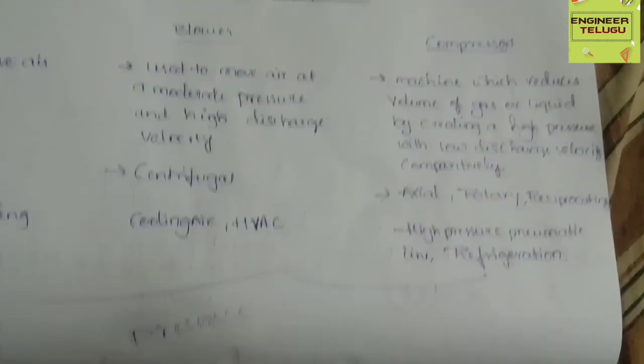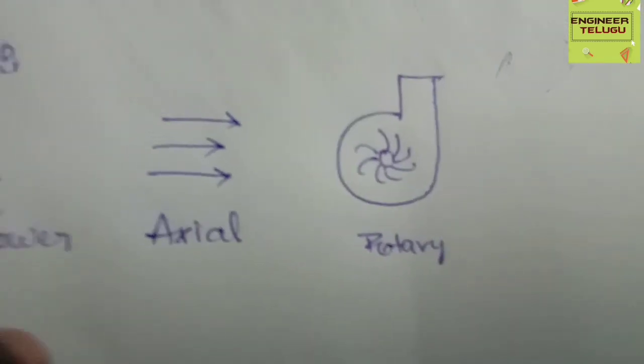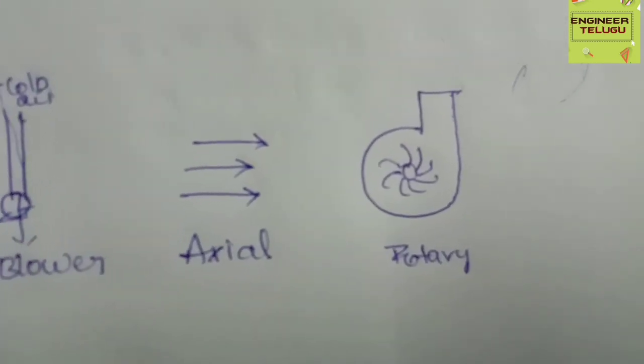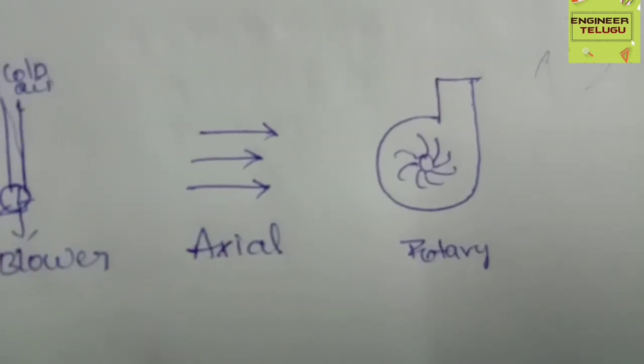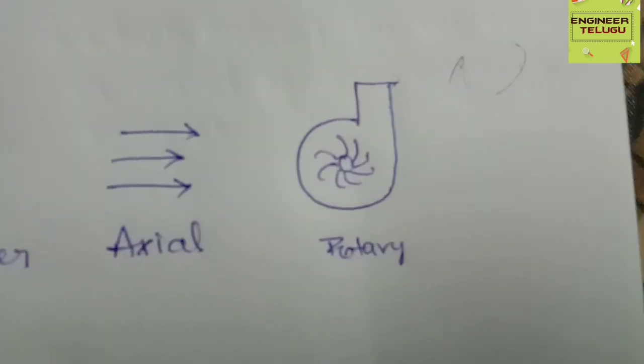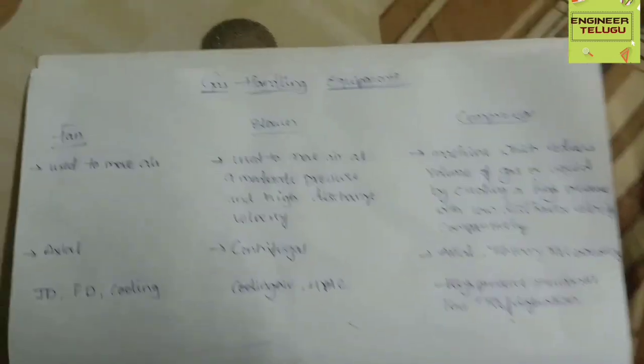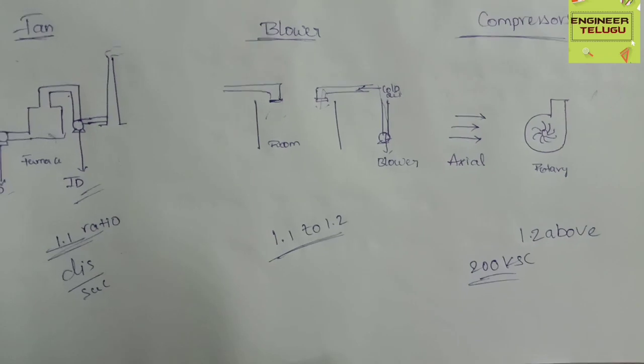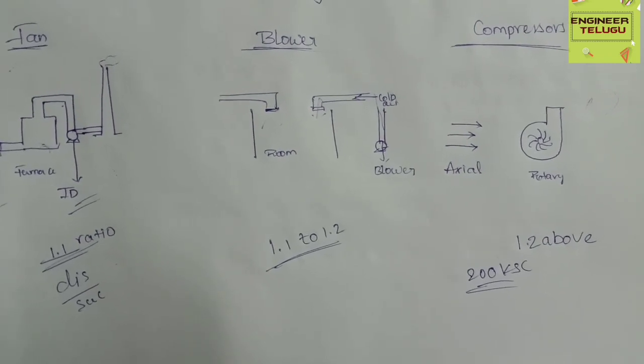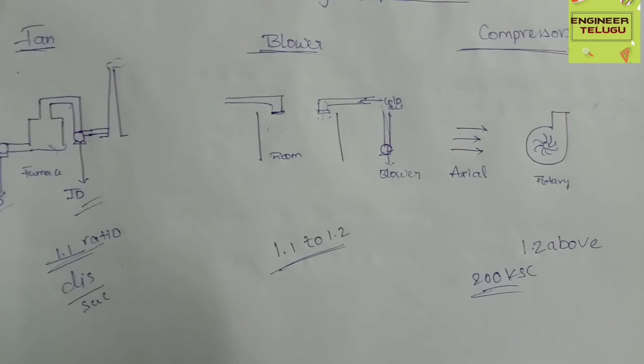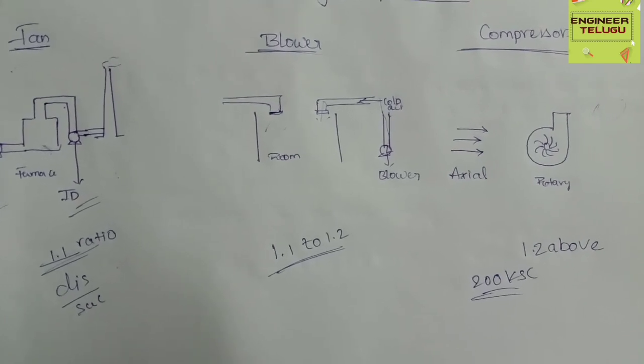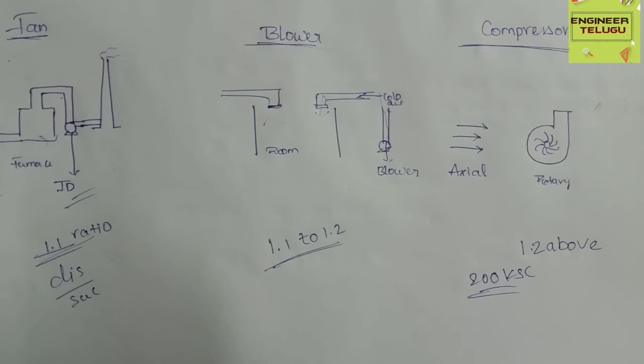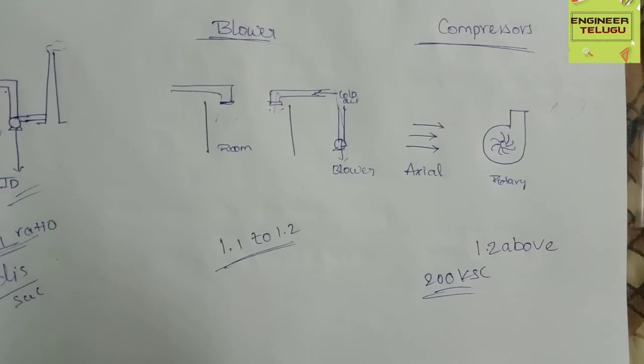We can use a centrifugal type blower, and for fans we can use axial fans. For compressors, axial, rotary and reciprocating — also called positive displacement compressors — are available. The main differentiator is the discharge-to-suction pressure ratio: fan is 1.1 times boost, blower is 1.1 to 1.2 with high velocity, and compressor is above 1.2 boost.